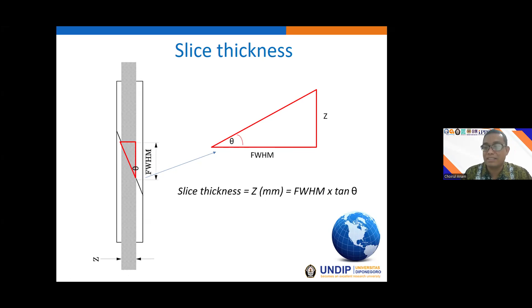The slice thickness is the full width at half maximum length of our image of the line of the wire, multiplied by the tangent of the angle. It is 23 degrees. So basically it is very easy to obtain the slice thickness using the Cat-Phan tool. We have the 4 lines here, this one, and this one, and then we measure the length and multiply by the tangent of 23 degrees.